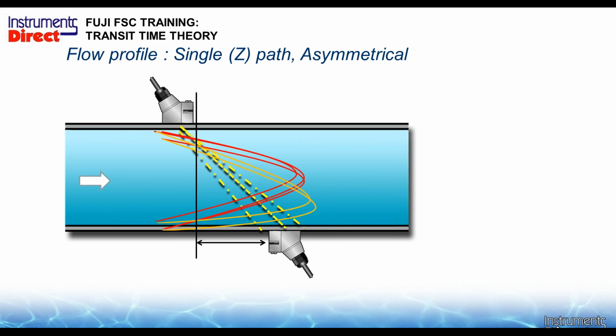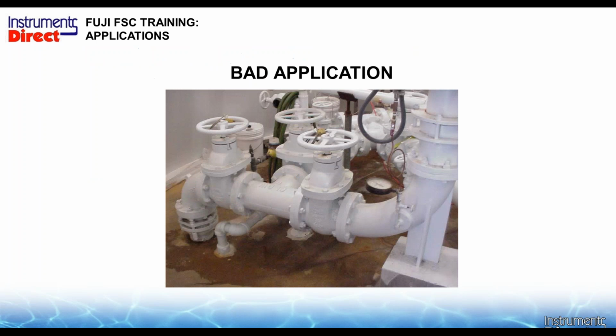As you can see, in an application where I have a short run of pipe and I have a very wide range of flow, a very high flow and very low flow, the points of transmission across the pipe can actually be in multiple points there. So you may have to move your sensor as the flow rate changes. So that's not a good thing, especially for a dedicated device. With a portable device, I may get a phone call that, hey, I put it on the pipe on Tuesday, and then I came back the next Wednesday, and lo and behold, I couldn't get a reading. And the first thing we'll ask is, did the flow rate change? And they'll say, yeah. So did the point of transmission across the pipe change, and because I had a short run of pipe, that can be an issue there.